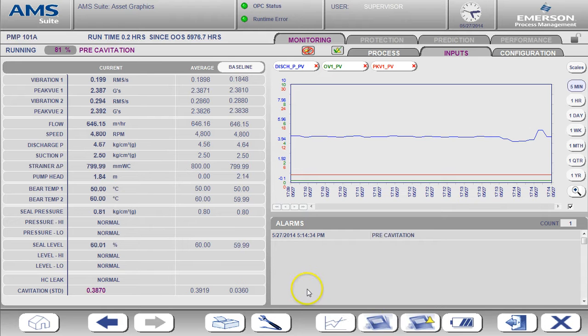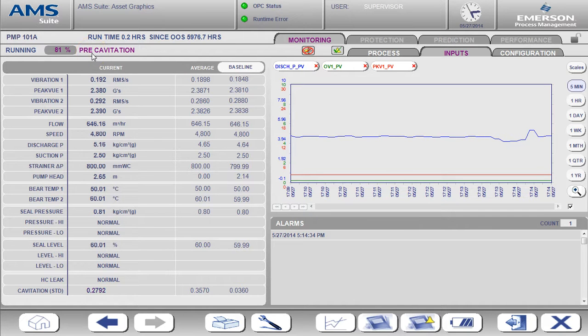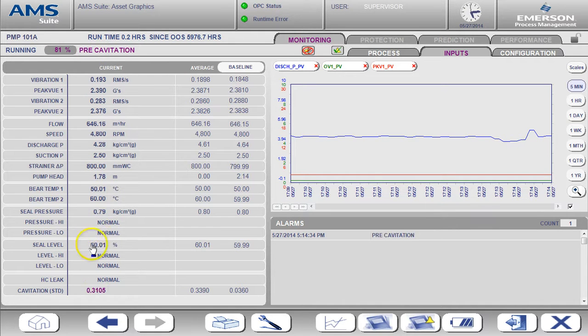The active alert is now for pre-cavitation. This is a warning alarm, as indicated by the purple text. To understand what triggered this alert, I'm going to add one more value to the trend.